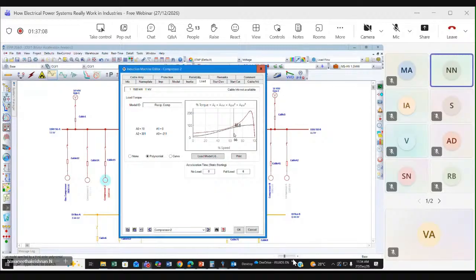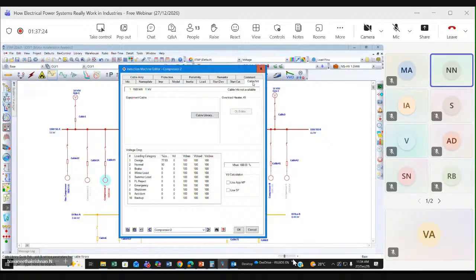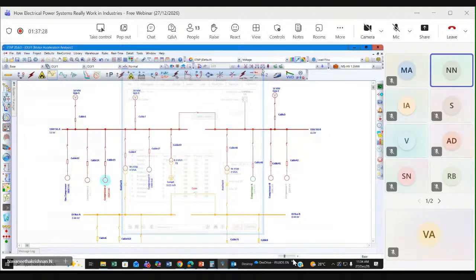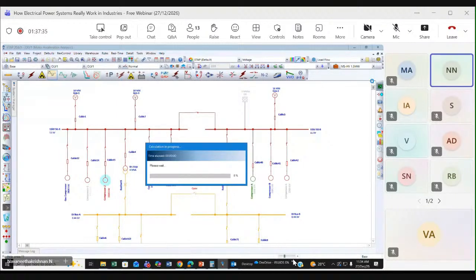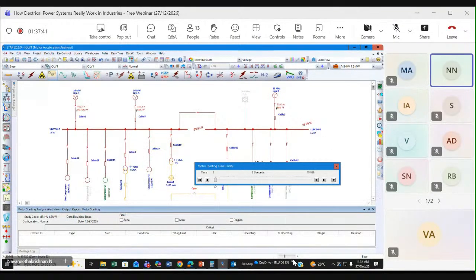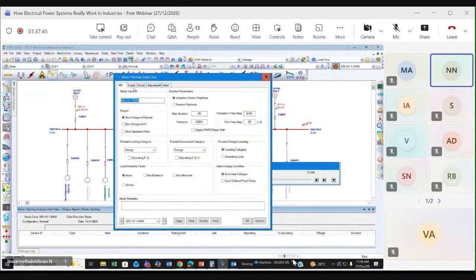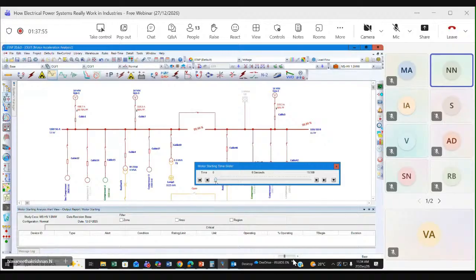If this curve is a little above this curve, the motor will not start. So we will model all this. Cable length is very important. Cable size is very important. All these parameters. Motor starting analysis: let us see whether the motor is starting or not. So I'm starting this motor. You can see here the motor is modeled. All these parameters we have given here. So then we started. Now I'm going to start.